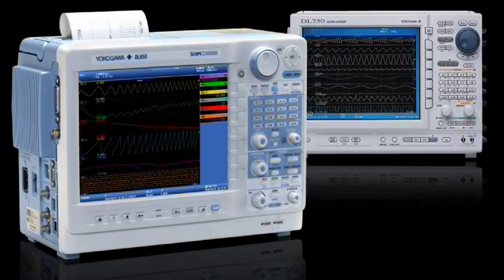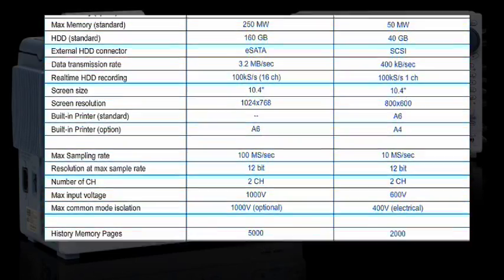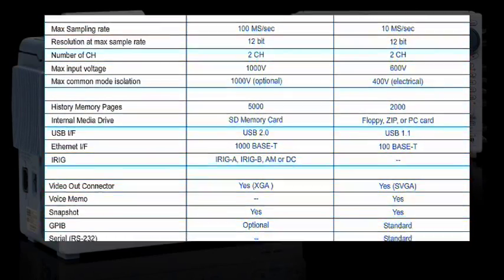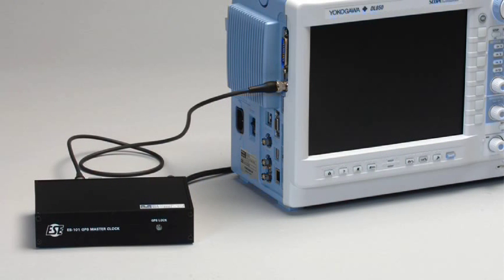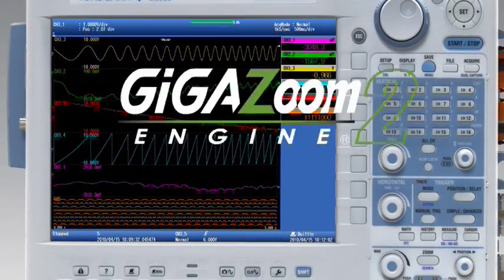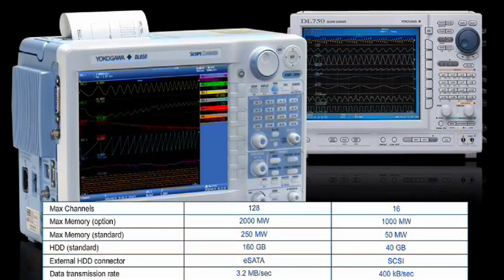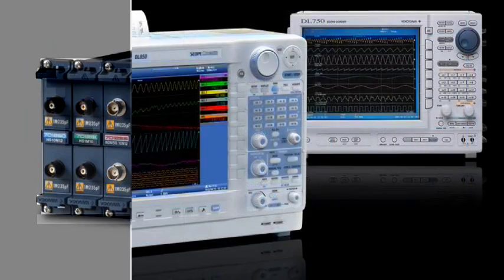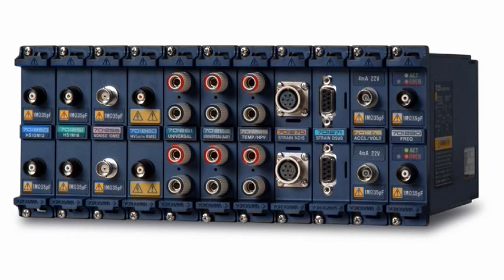The DL850 boasts improved performance over its predecessor, the DL750, in nearly every area. Major specifications like sample rate, memory, channel count, screen resolution, and data transfer rates are all significantly improved. New features like IRIG synchronization and streaming to external disk have been added. The DL850's completely redesigned GigaZoom 2 engine allows for real-time zooming during acquisition, with zoom factors up to 10 million times. More than 100 minor specifications are improved, like history timestamp resolution, backlit channel buttons, and many more. To preserve your investments, the DL850 is backwards compatible with all DL750 modules.